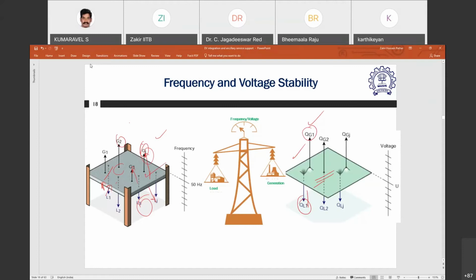And in the frequency case, you do not have an option to have the frequency below, let us say, 47.8. It will vary from grid to grid depending on the protection settings. For example, in simple understanding, below 47.5 or 47.8 hertz, even in dynamic conditions, the grid cannot survive. So the minimum frequency that potentially you can achieve is 47.8 in the worst possible case. I'm just giving an example. Beyond that, the grid will simply collapse and the frequency will simply go down to zero. While in the voltage, that's not the case.